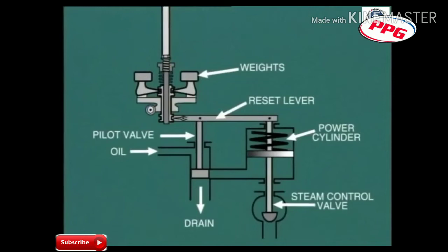In this configuration, a change of turbine speed causes the centrifugal weights to move. For example, a decrease in speed causes the centrifugal weights to move inwards and lower the pilot valve.